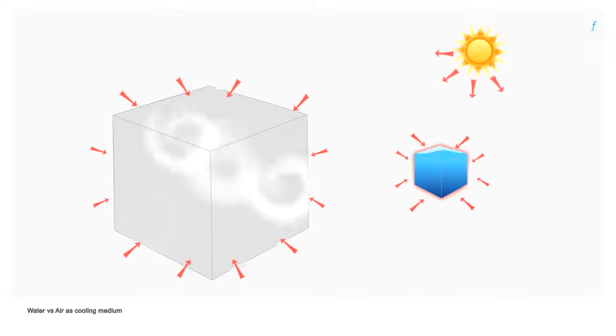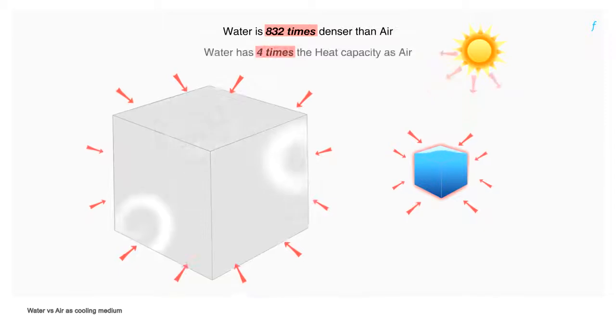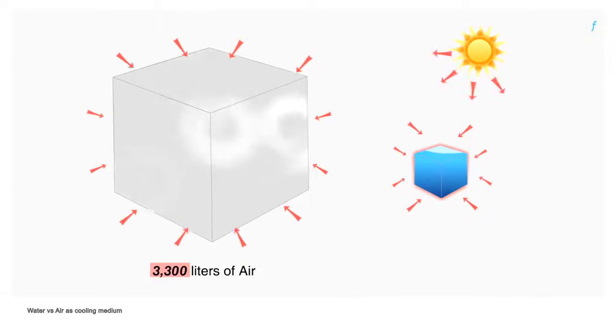Water is 832 times denser than air and has approximately 4 times the heat capacity as air. Effectively, one must circulate 3300 liters of air as opposed to 1 liter of water to absorb the same amount of heat.